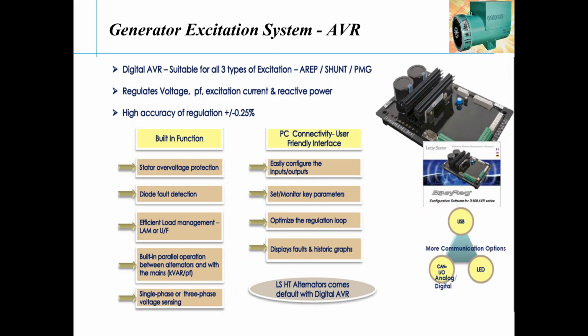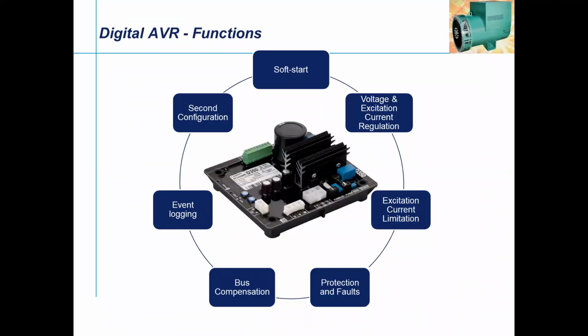Displays and faults, it has its own advantage, like giving the events log or faults, and the historic graphs we are able to extract. All you can say, demand this from the digital AVR. So this is a soft start. I was just mentioning earlier, you can do all this: soft start, voltage excitation, current limitation, protection and faults, bus compensation. All these things earlier they were doing with different devices. Now this AVR is going to give a communication to the system where you have a fault. So it is more of an integral system of the generator now.